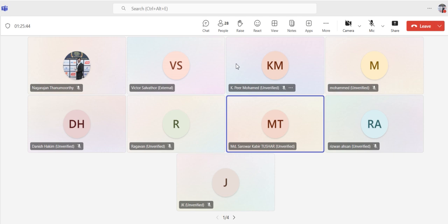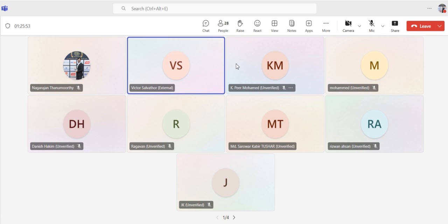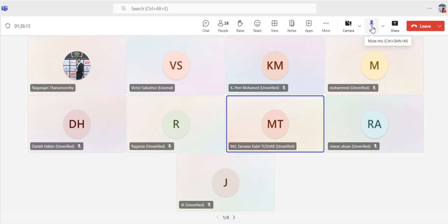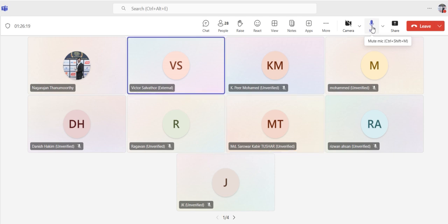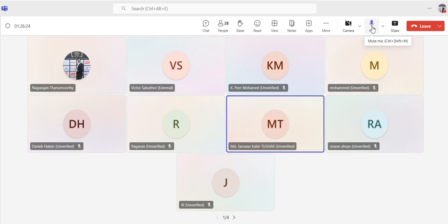Then sir, the chiller loss, where will it be added, in the primary system or the secondary? The chiller loss is based on the manufacturer. For example, you have a chiller capacity of 10 liters per second. If you go to the manufacturer, they will give the selection data. In the selection data, the water pressure loss will be there. Maybe it will be around 5 to 10 meter head, and it will vary based on capacity. In which system will we add this, primary or secondary? You have to add it on both sides because it's a loop. Yes, okay, I got it.